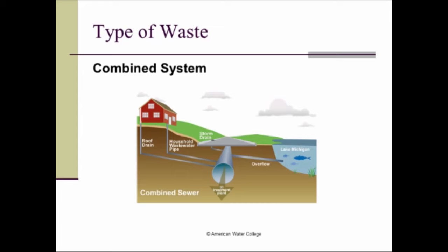In the case of a combined system, household waste, roof drains or surface runoff, and storm drains or road runoff all go into a common pipe. As that fills the pipe up, it will overflow into the natural waterway. Under normal conditions, as long as the pipe is not overloaded, both the runoff and the sanitary waste will flow to the wastewater treatment plant. But when it reaches full capacity, the overflow goes into the natural waterway — a combination of surface runoff and sanitary waste.